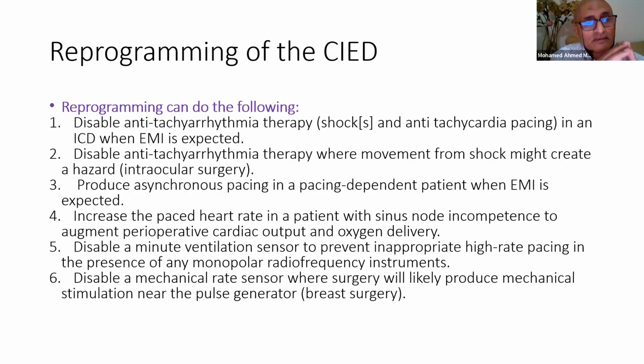Also, if the device has synchronous pacing of the heart, we need to convert this synchronous mode into asynchronous mode, because the synchronous pacing will sense the electrical activity coming from the diathermy as if it is electrical activity coming from the heart. And as we said, it will either pace the heart at a higher rate, or it will stop pacing the heart, and the cardiac output and the heart rate will be very low during the period of use of the diathermy. So we need to turn the device from synchronous to asynchronous.